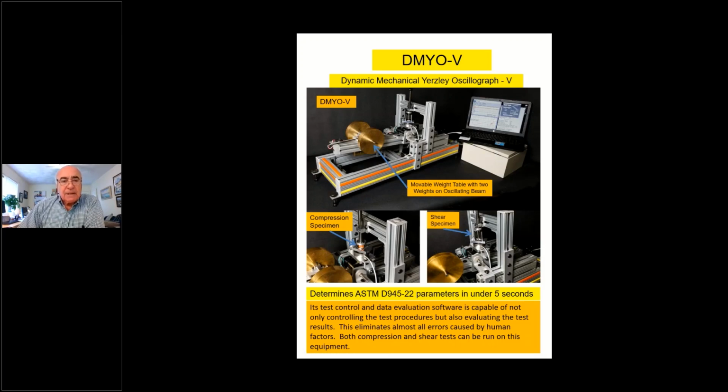And these weights can be up to 4. We can travel this table during the dynamic test and bring them to any point, so incrementally changing the moment of inertia of the equipment.